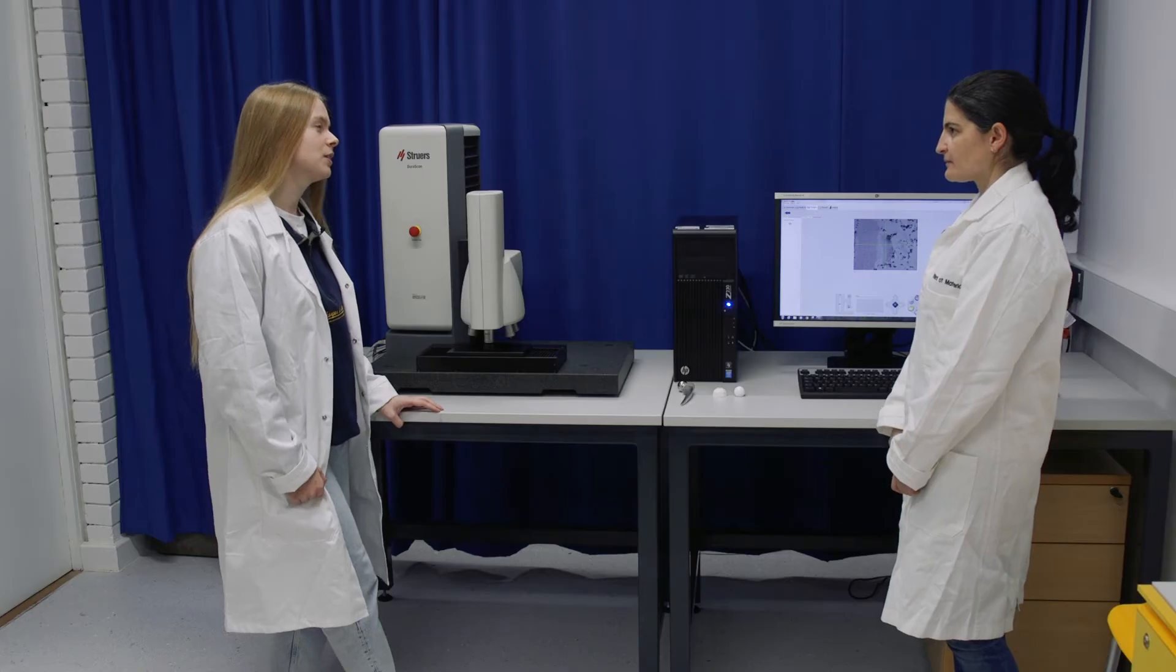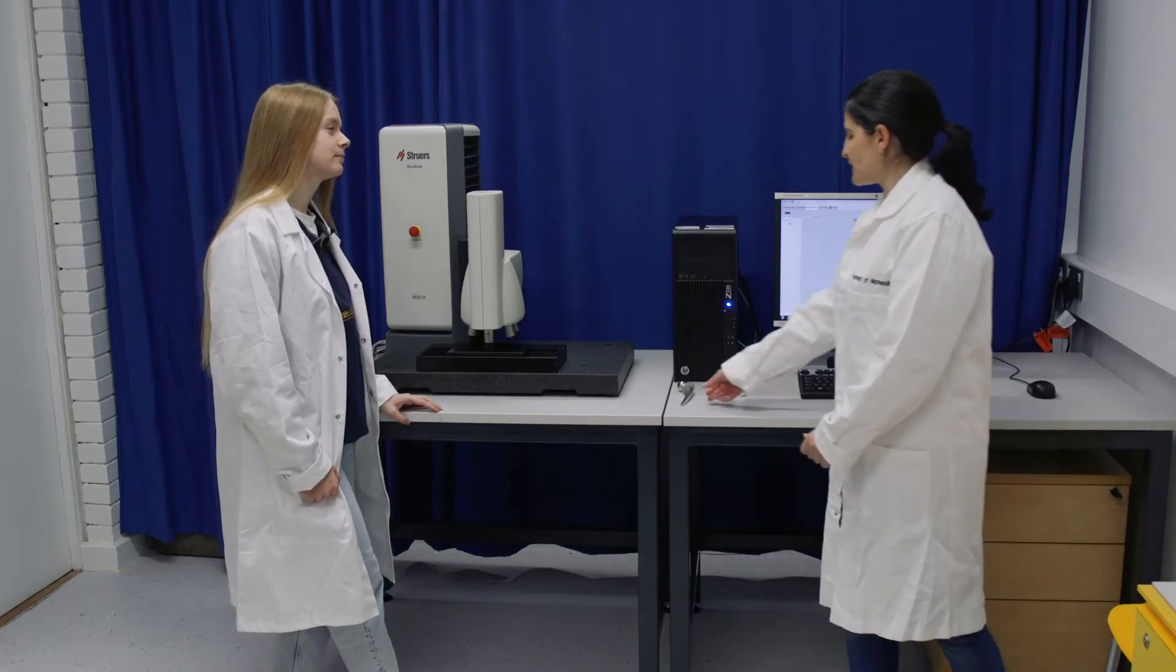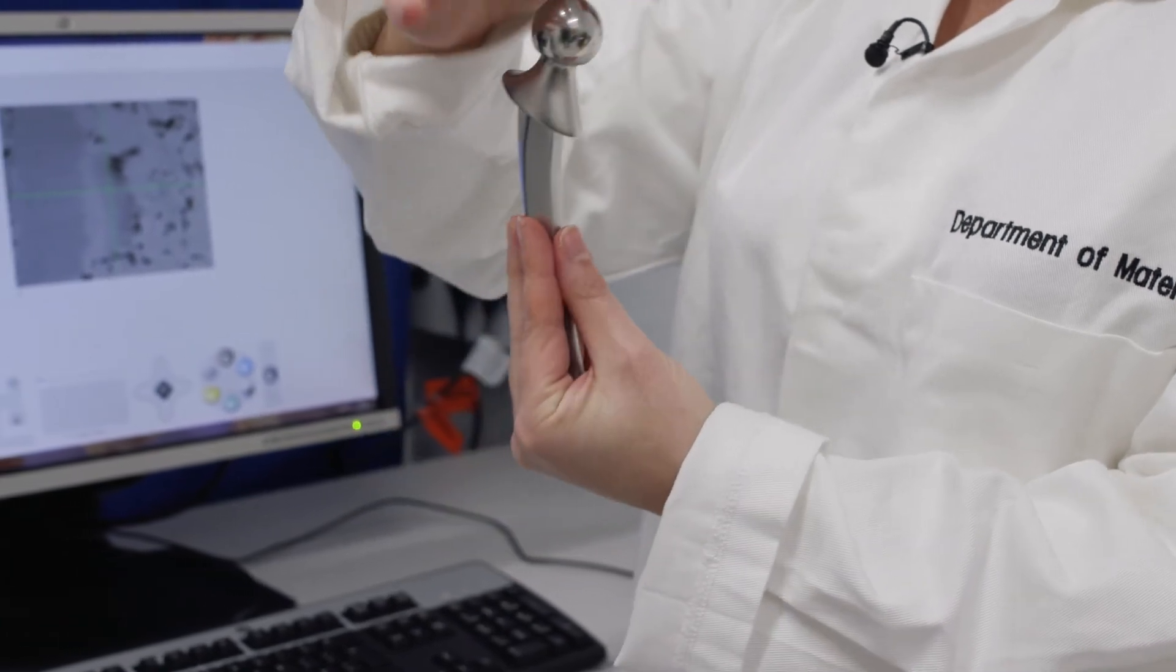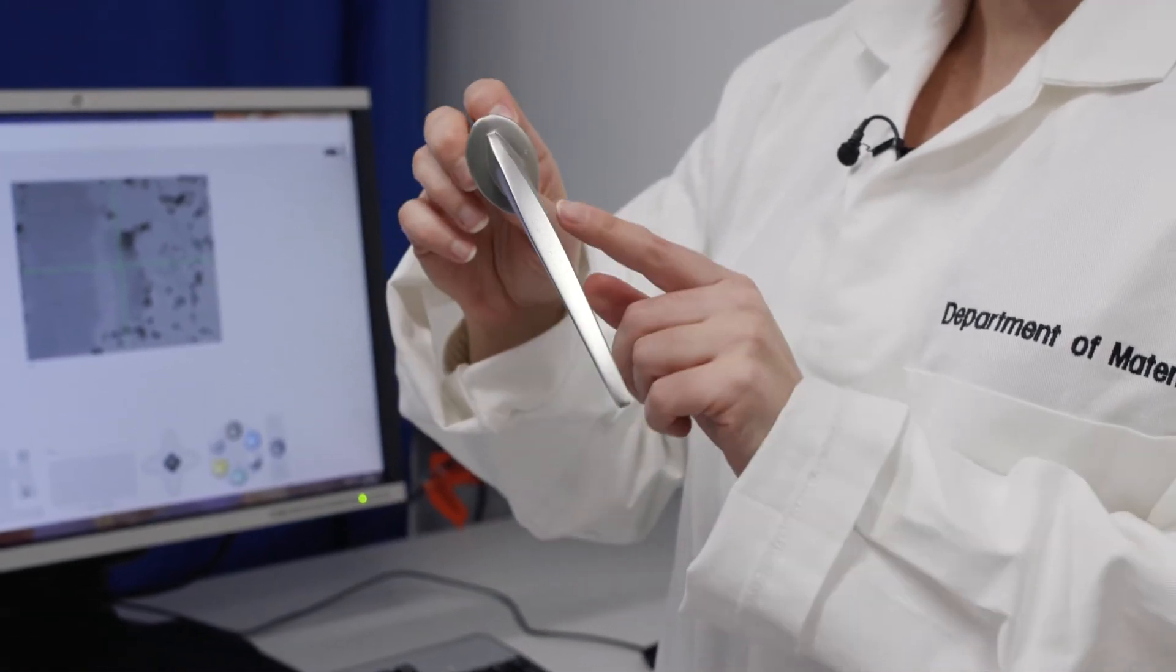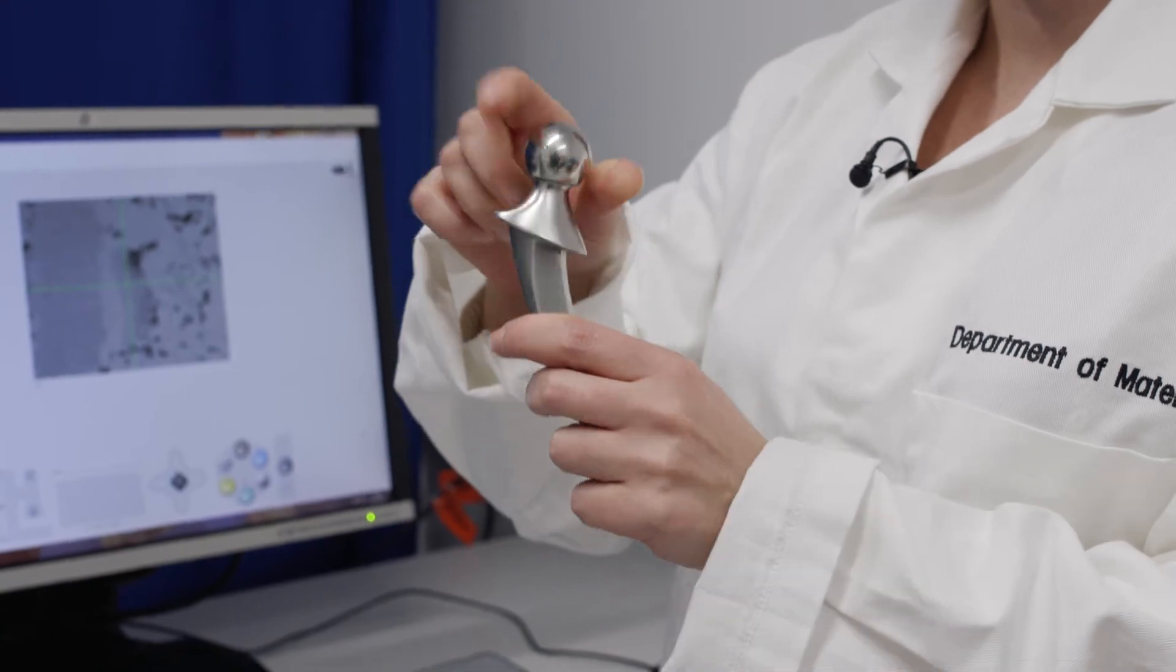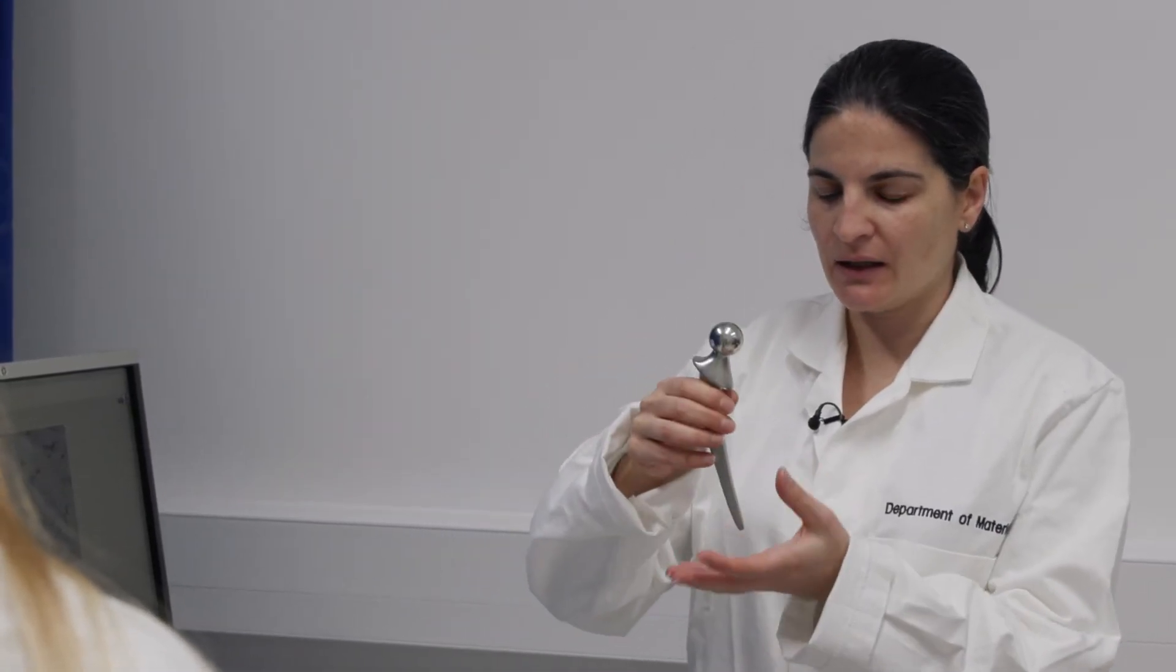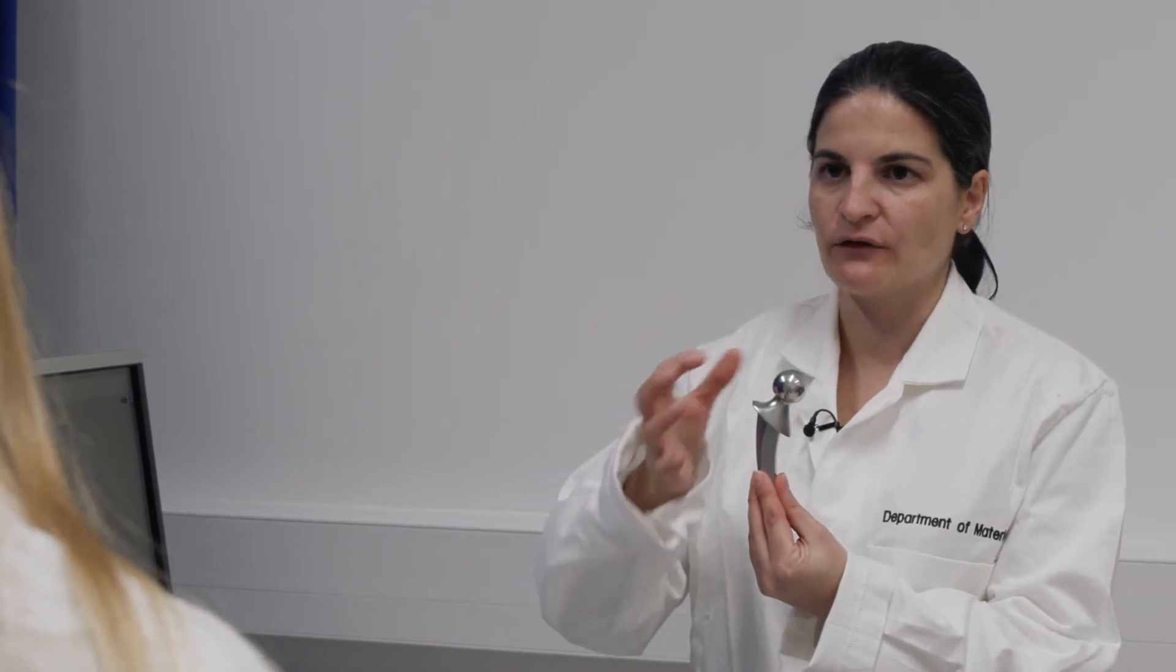So when we're developing new materials and medical components, how do we know that will work? You can test the mechanical properties of the implant. For example, you can apply a load on the system, do a compression test. You can study if there is a fracture in the stem of the implant or maybe the head of the implant. That is important because the hip implant has to sustain the weight of the patient.